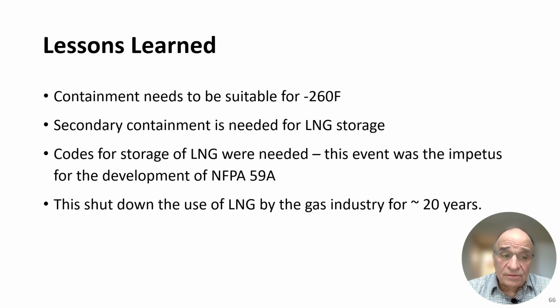Lessons learned, just to state a few of them, because there were many lessons learned. Containment needs to be suitable for minus 260 degrees Fahrenheit. Secondary containment is needed for LNG storage. Codes for storage of LNG were needed. This event was the impetus for the development of NFPA 59A. This shut down the use of LNG for the gas industry for approximately 20 years. Another gas LNG facility had not been built for a 20-year period.